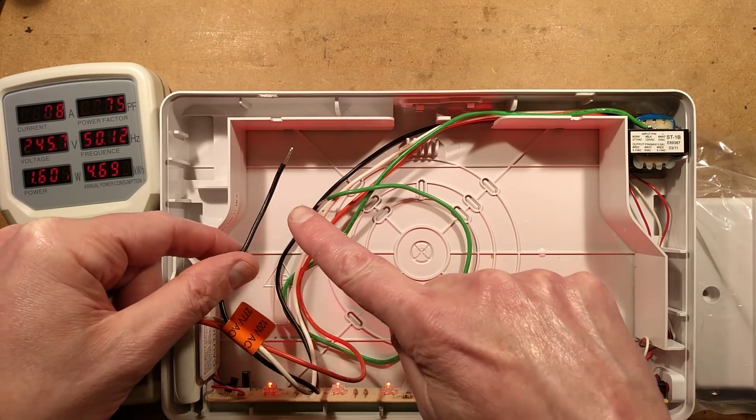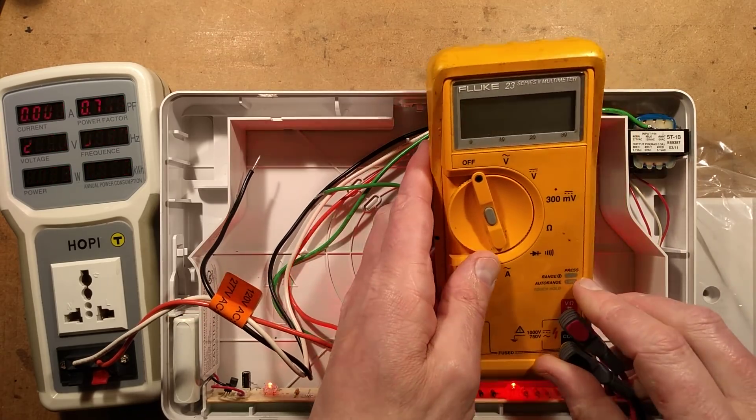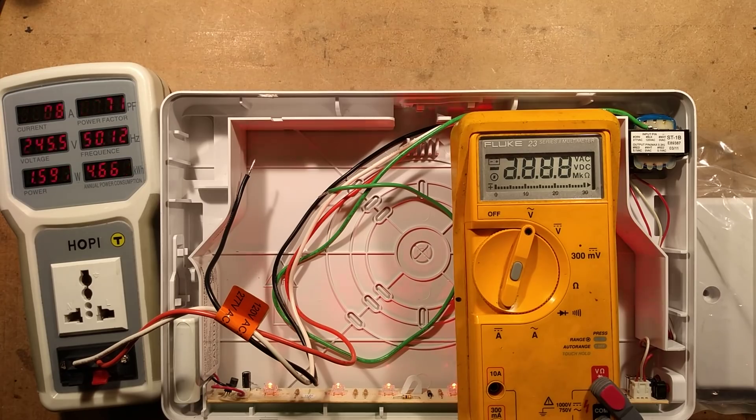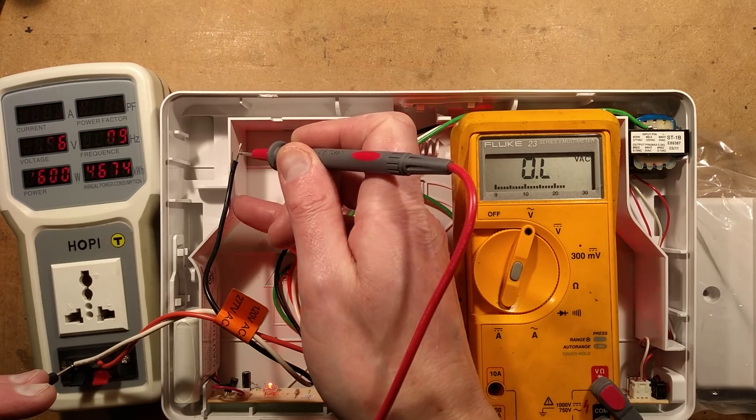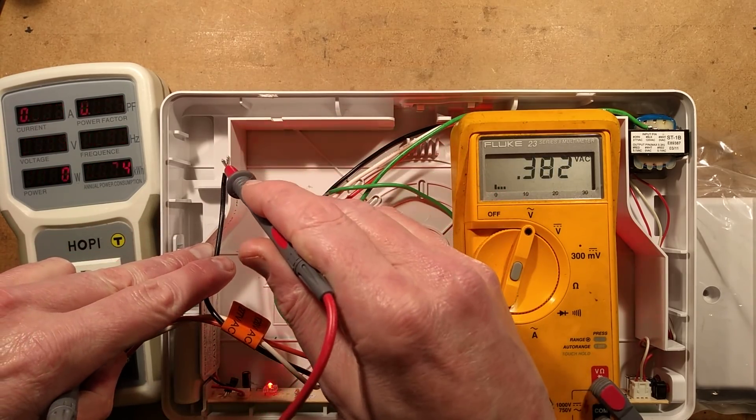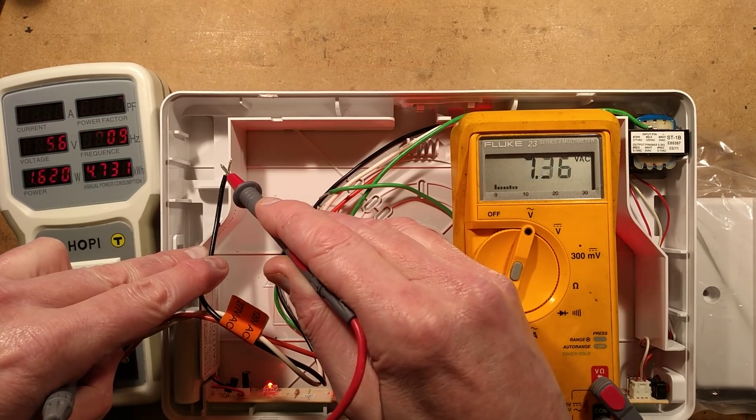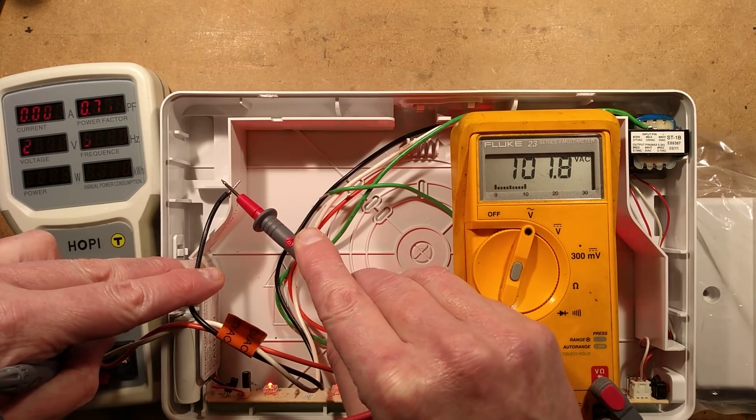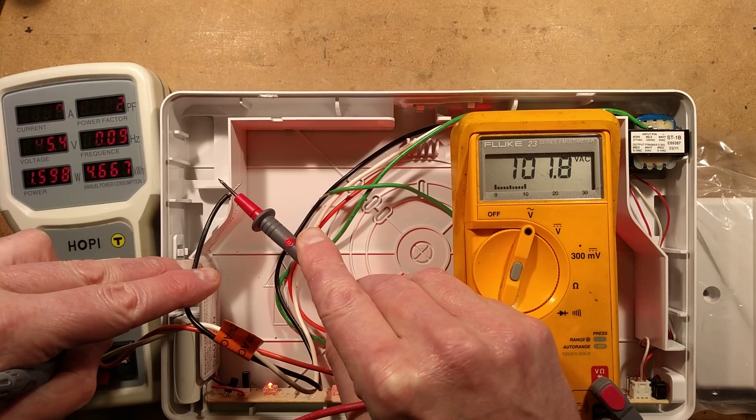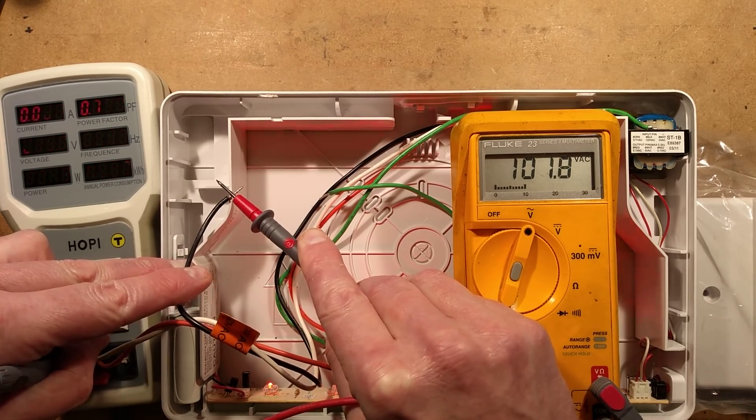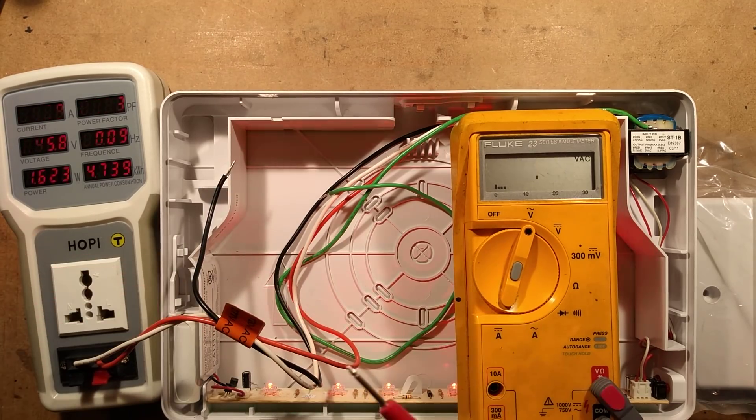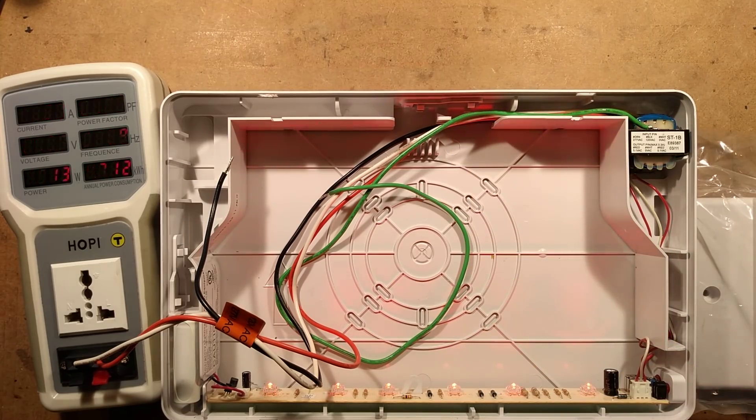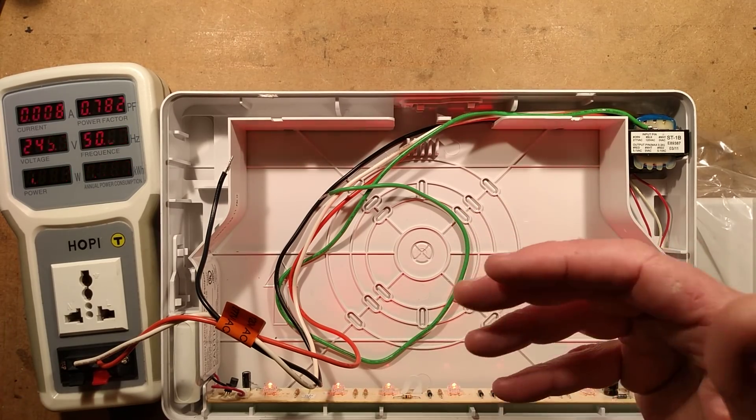I was picky about keeping this wire out of the way. If I bring a meter in and connect it to AC volts between neutral and that wire, I'm getting about 101 volts. That's because I'm feeding the 277 volt winding with 245 volts, so the 120 volt winding is giving out just over 100 volts.